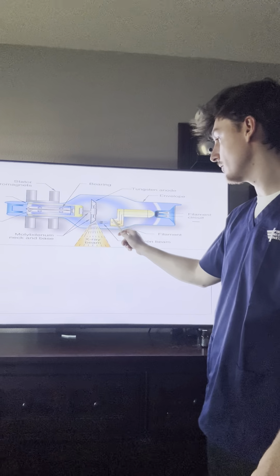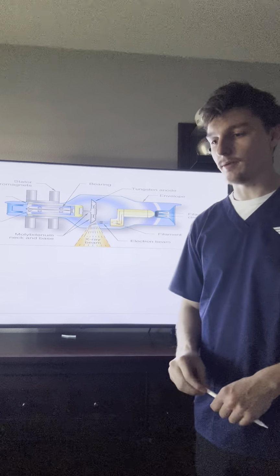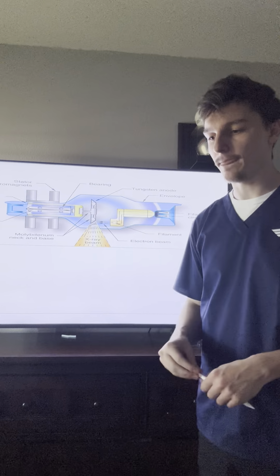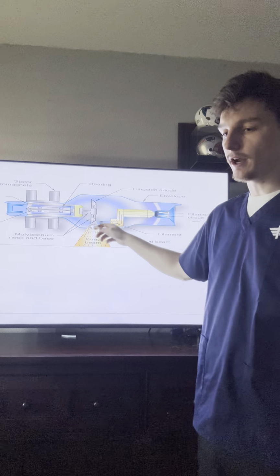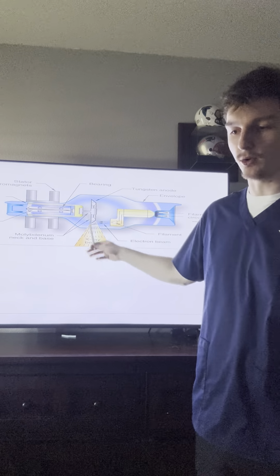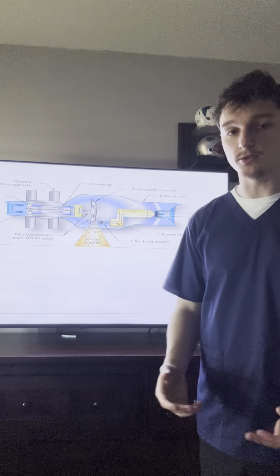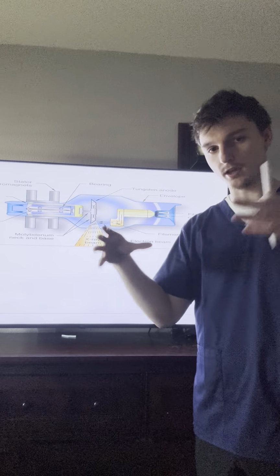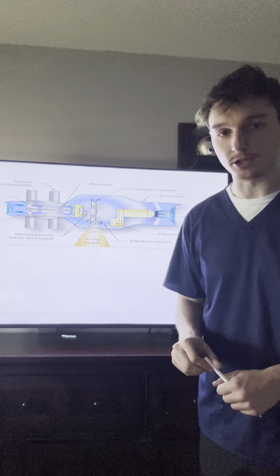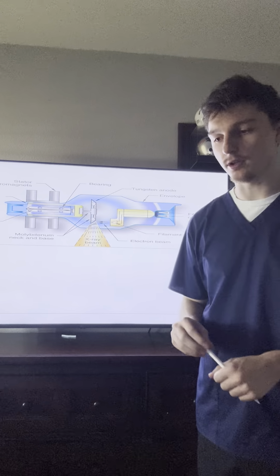Target angle right here is 12 degrees, and it'll help everything flow. It'll help the movement from one spot to the other, and when it hits the target area, it bounces out the effective focal spot, which is what we'll be using on the patient. It's going to be like the light focusing on whatever we're x-raying on that patient.